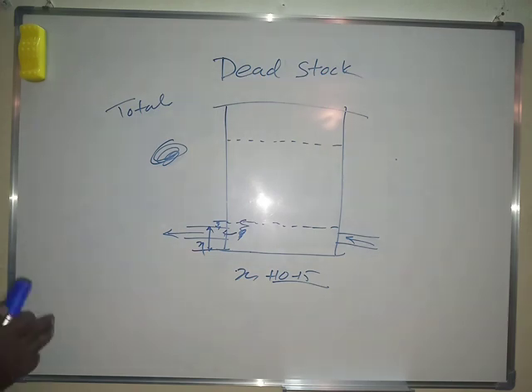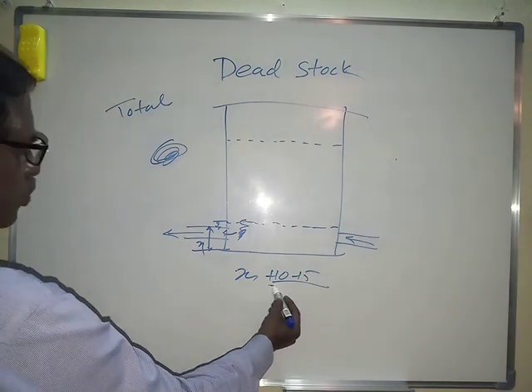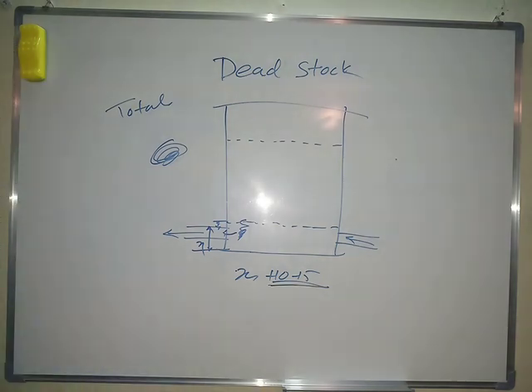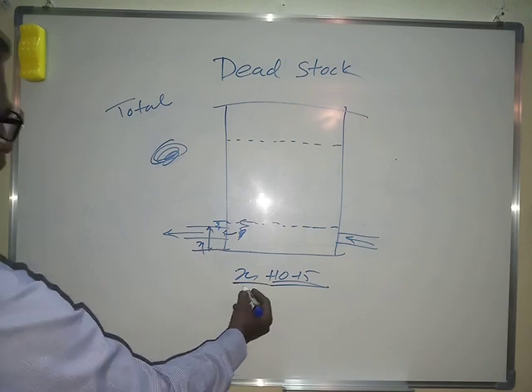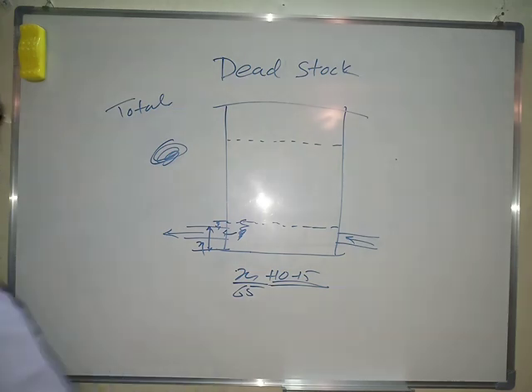At the gantry when you are loading a truck, your flow meter may give an erroneous reading. So that is why the general thumb rule is up to 10 to 15mm you should allow. And this X, as per API 650, if you see, is always up to 65 centimeters or 650mm.